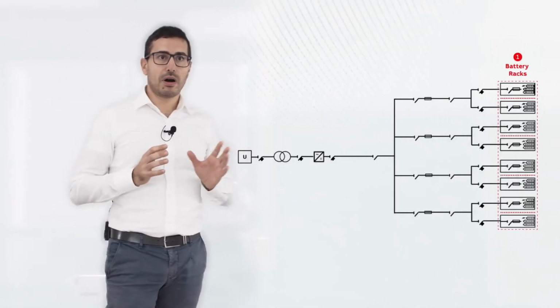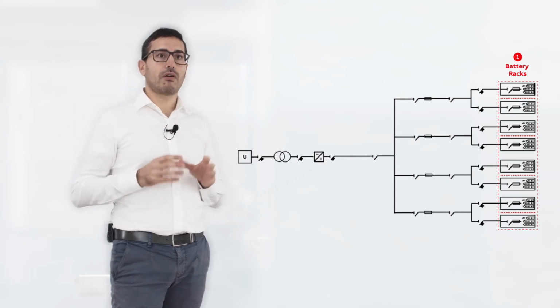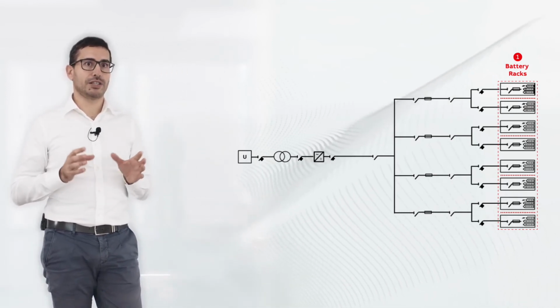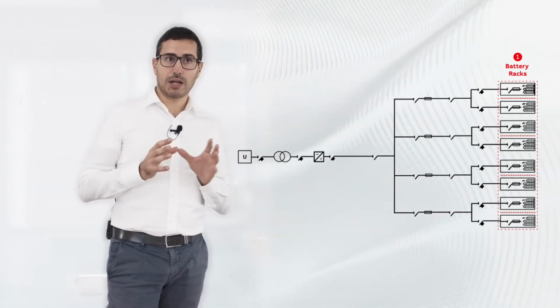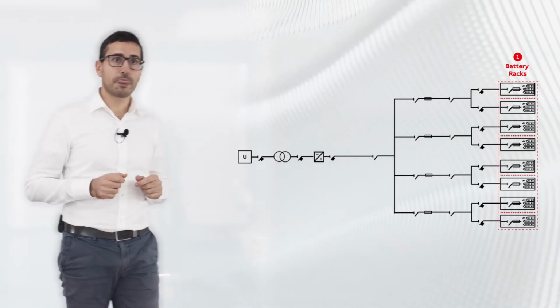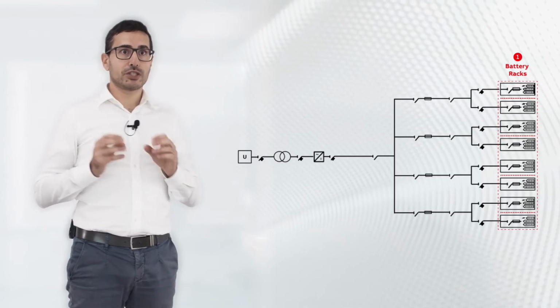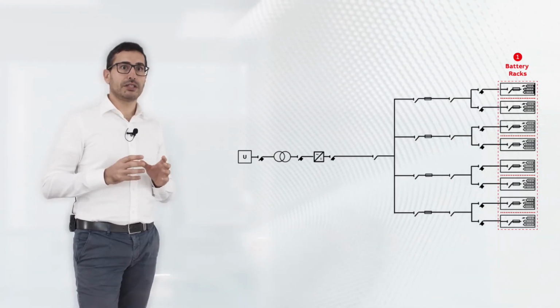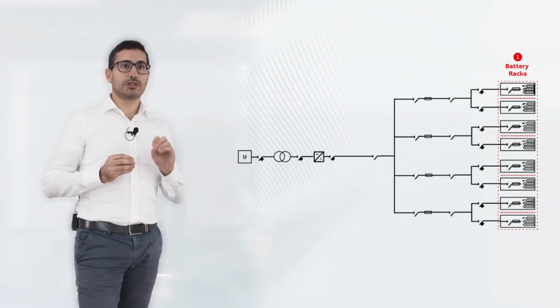Let's now focus on the battery racks. The battery racks in our system may be around 20 different battery racks, which are arranged then in a 4 modules containerized architecture. Each battery rack provides the battery modules, in our case lithium-ion batteries, together with an appropriate protection and switching device. From a safety standpoint, it's extremely important to select the proper device to protect and switch the battery rack. In our specific case, a multi-level protection is provided, having fuses at cell level, rack level, plus a switch disconnector, which combined with the fuse protect from overcurrent and short circuit the battery rack.